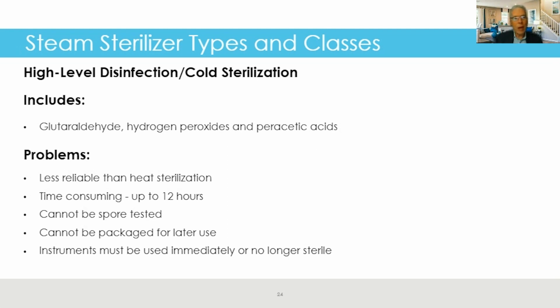First of all, I'm not a real fan of it. I really don't recommend sterilization or high-level disinfection because the chemicals are quite hazardous - glutaraldehydes, hydrogen peroxides, peracetic acids. The other inherent problems are that they're less reliable because they're time-consuming. Typically the instructions for use would say 12 hours - well, how do you know it's really been in there 12 hours? You can't spore test it. The other problem is you can't package it and use it later. You have to literally take it out with sterile tongs, rinse it off with sterile water, and use it immediately. It's just not a practical solution in a busy dental office.